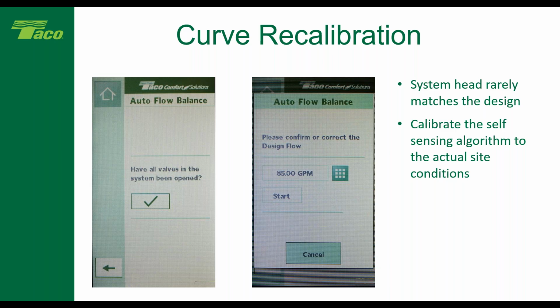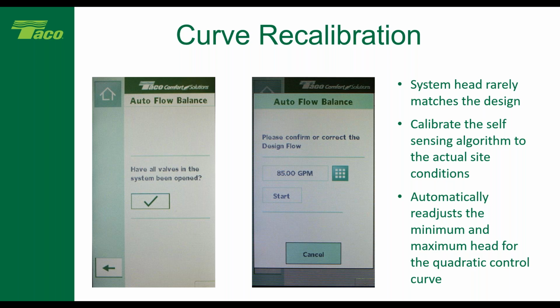The nice thing is, if something ever happens that the building changes, you add an air handler, you add piping onto the system, you do an addition to the building and you use the same pumps, now I can go back and I can recalibrate based on the new conditions. How many times do we design a system that we put pumps in knowing that there's going to be an expansion, but that expansion may not be for a year or two? So you need to calibrate it for the condition at that point, but you need to go back and recalibrate when the building addition gets put on. So what this does is recalibrate or readjust that min and max head for the quadratic control curve. And it does it easily. I can do one in about 10 minutes. That's how easy it is.